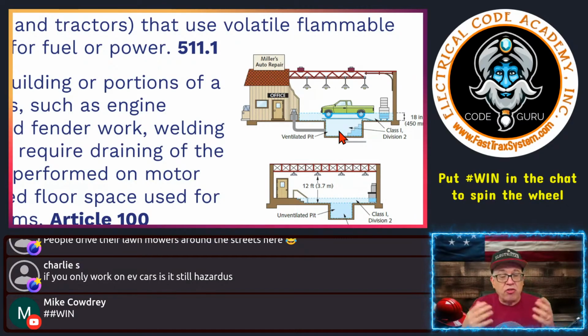So that also goes for different types of equipment - much more expensive equipment in a Class 1 Division 1 than in a Class 1 Division 2, right? So it can be a huge cost difference. It may behoove us to install a ventilation system in the major repair garage area in order to reduce the classification because of the wiring methods.